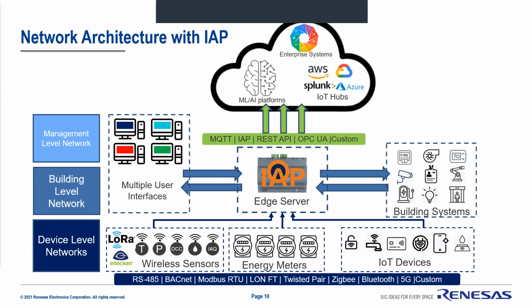A few examples of what you can do now that you have multiple systems on a common data layer. A good example is taking an intelligent lighting system that dims and controls based on occupancy and light levels, and integrating it with a fire alarm system. Why integrate those two things? A great example is creating a specifically lit egress path during a fire alarm event, so the lighting system can direct people to an exit more efficiently.